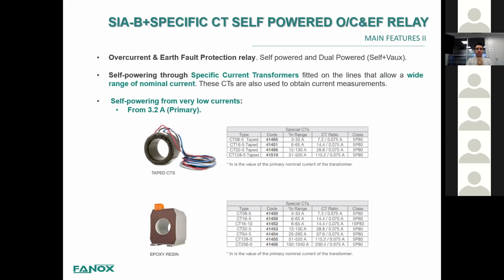These relays, I told you, work with the specific CTs. That means that there's a high saturation range. So for example, if you choose CT32 tap, the nominal current of the system that it can control is between 12 and 130 amps. That means these CTs can be used to standardize the engineering part. So you can use the same relay with the same CT for a wide range of installations with different nominal power and currents. This is very helpful because you have to do the engineering. Also, it has some advantages in terms of stock and warehouse components.